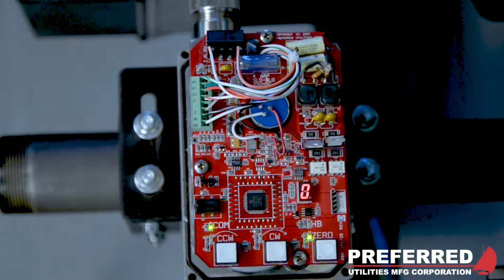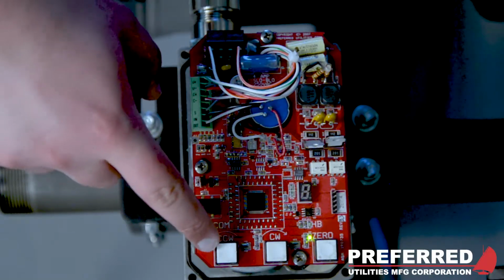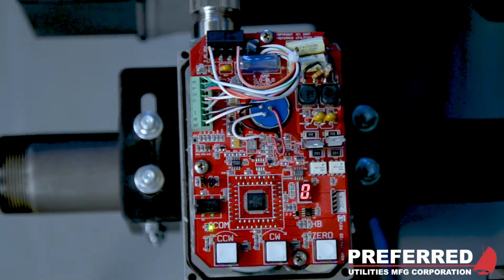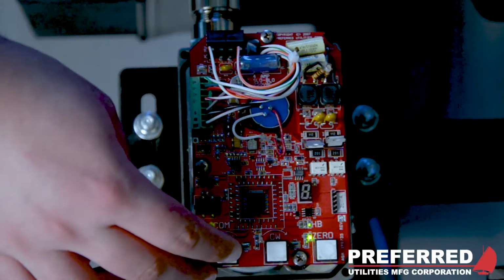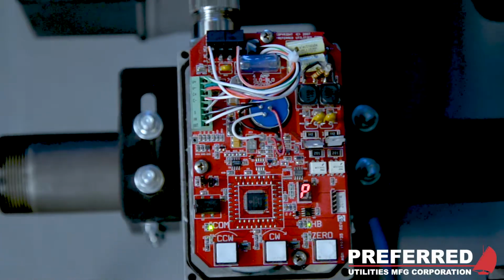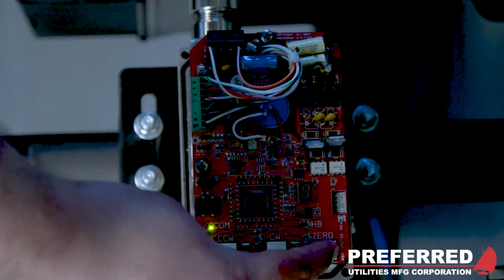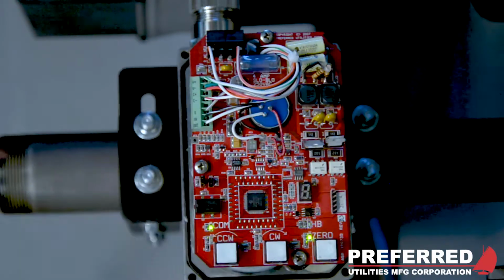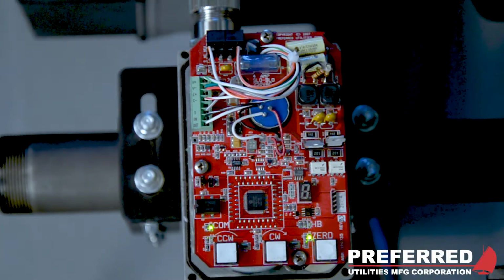So now that we have enabled the zero calibration at the controller, we need to perform the zero calibration at the servo. To do this, you'll now find that your clockwise and counterclockwise push buttons are active, and you can manually control the servo. What you'll want to do is make sure your servo is in the farthest closed position, and this will be your zero position. Once you are fully closed, you want to hold down on the zero button and hold the direction of your closed position, then release both. And that will complete your zero calibration.